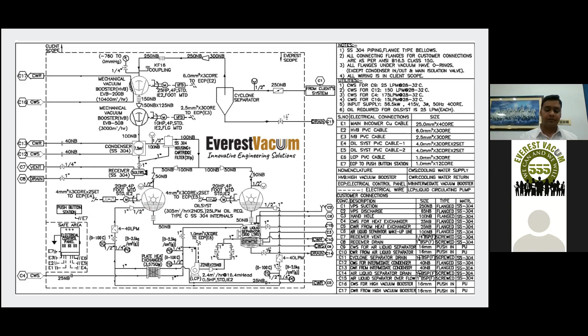Through a recirculation pump, we have a PHE, plate heat exchanger, connected, which helps in cooling down the temperature of the recirculated oil and feeds it back to the oil assist vacuum pumps. So what we are doing here is actually saving on your sealant fluid, reutilizing in an efficient way the fluid being circulated inside the pumps.